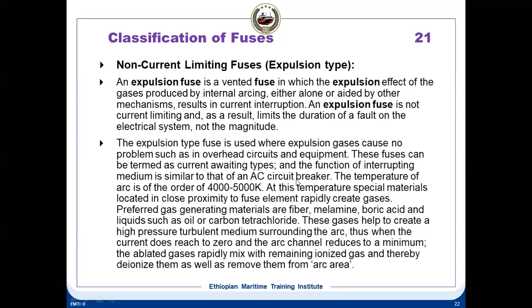And another one is this vacuum type. Vacuum means it is just vacuum inside. It is not an expulsion fuse, but still a current zero waiting type because of the dielectric. The dielectric properties of the vacuum are much more than the air. So this dielectric property of the vacuum will be very high, and it interrupts the arc. So the main difference is that it's a completely sealed unit and no expulsion action. Vacuum fuses are totally sealed, and interruption occurs because of the rapid dielectric buildup that occurs in the vacuum after the current zero is reached.